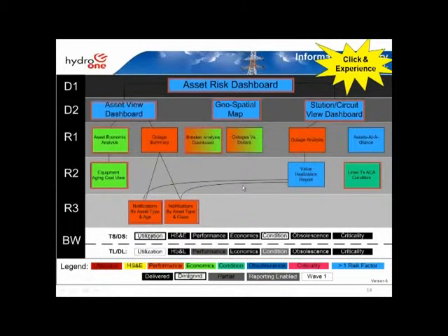And you can see again in performance that the benchmark is performing 2.5 times worse, and it's basically saying that the transformers are the root cause of that problem. So the outage frequency is 0.6, and the benchmark is actually 0.2 outages per year. So this is drawing our attention. It's shining the light on assets that require our attention. It's helping us to build that business case that is defensible before our regulator.